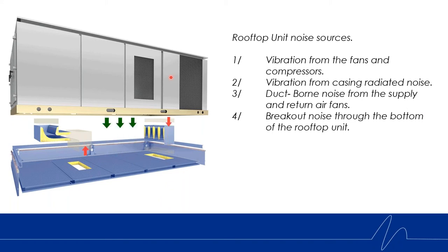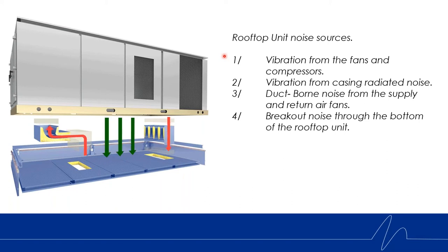Air conditioning units — rooftop units — are giant sheet metal drum skins with a lot of energy going on inside of them. So we have four main sources of noise control to worry about when it comes to an air handling unit. We obviously have vibration from the rotating equipment inside — there are fans inside, and compressors with rotating masses causing vibration. We also have vibration from the casing, what we call radiated noise — all that energy going on inside the sheet metal drum skin can radiate through the casing and cause a lot of vibration.